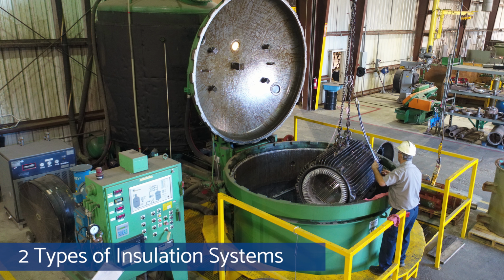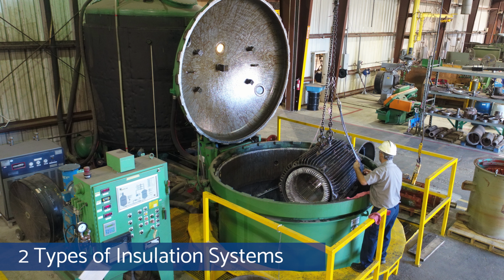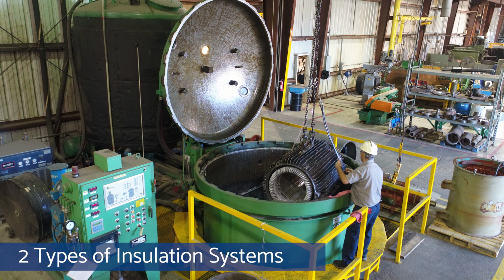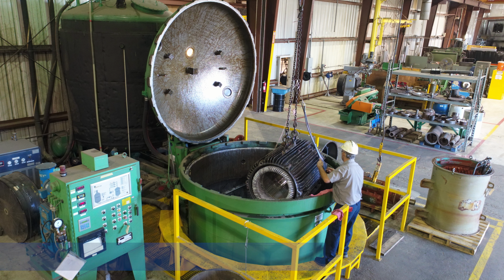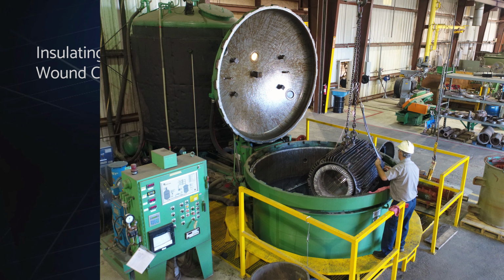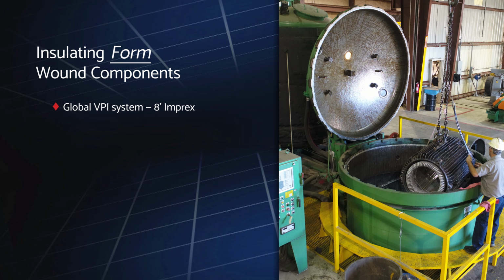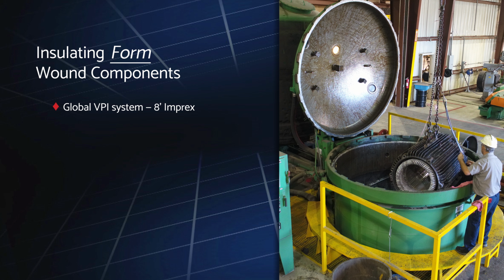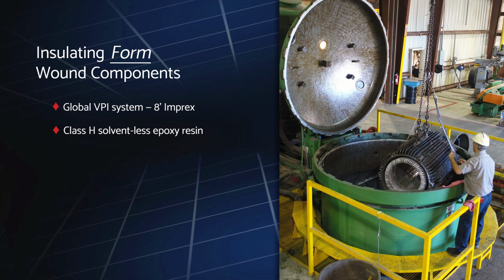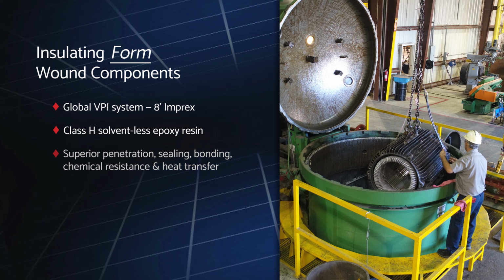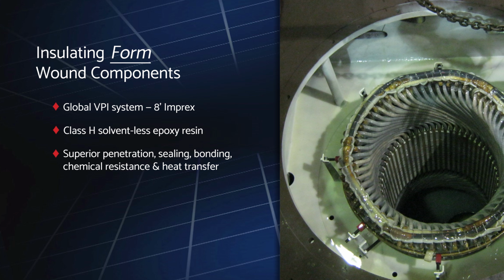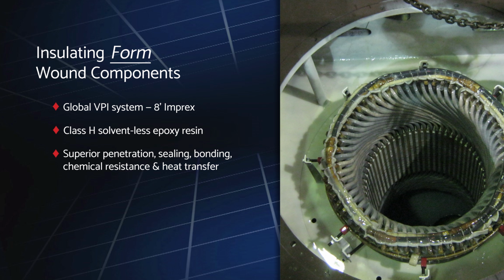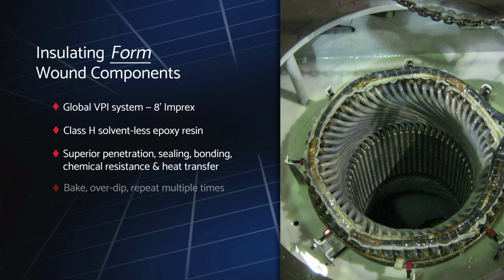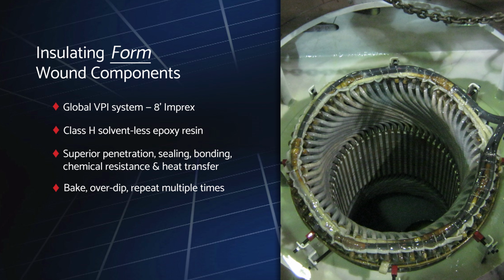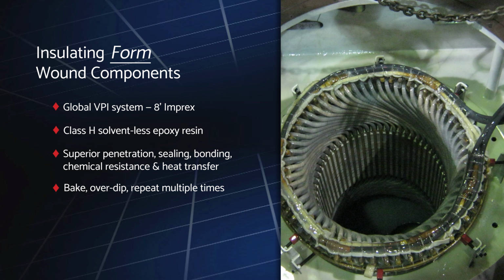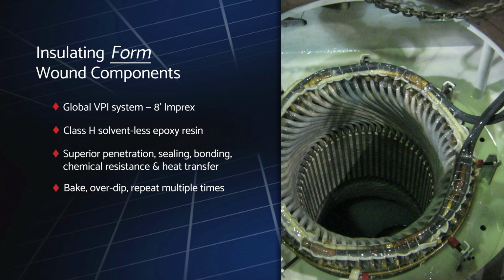To ensure optimal reliability, Leonard utilizes two types of insulation systems, depending on the type of equipment. For form wound components, we utilize an 8-foot Imprex Global VPI system, featuring high-grade, Class H, solventless epoxy resin for superior penetration, sealing, bonding, chemical resistance, and heat transfer. The components are dipped and then baked multiple times to cure the resin for long-term electrical performance.